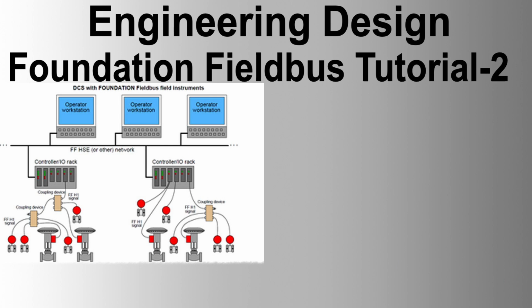View objects. A function block has many parameters, so it is not practical to read them one by one for display purposes. Foundation Fieldbus utilizes the FMS variable list concept for this purpose. A view object is a predefined variable list made of many block parameters. 4 view objects are defined for each block.